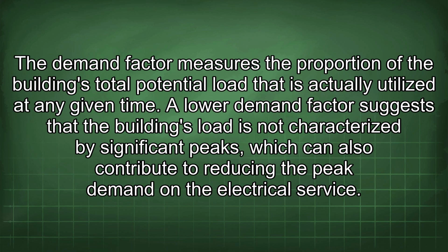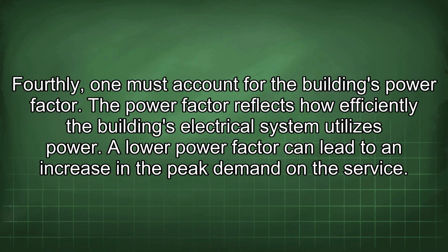The demand factor measures the proportion of the building's total potential load that is actually utilized at any given time. A lower demand factor suggests that the building's load is not characterized by significant peaks, which can also contribute to reducing the peak demand on the electrical service. Fourthly, one must account for the building's power factor. A power factor reflects how efficiently the building's electrical system utilizes power. A lower power factor can lead to an increase in the peak demand on the service.